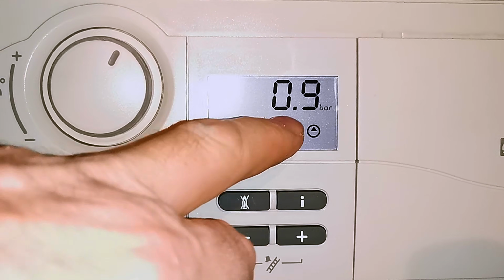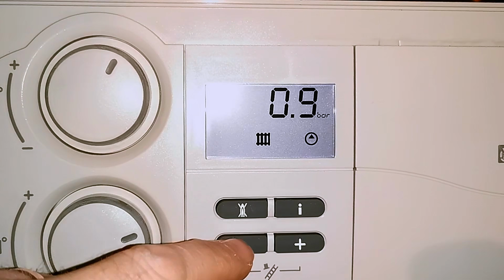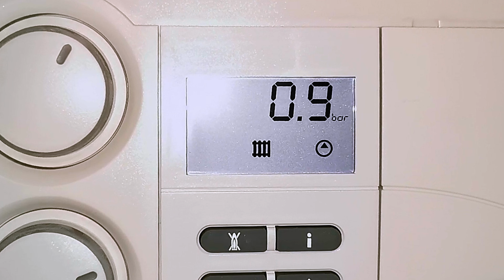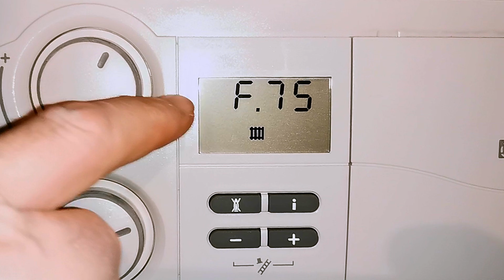Now, if that pressure does not change when the pump runs, then the boiler will lock out with F75. And there you go, the boiler is now just locked out again with F75. And that's because the pressure sensor has become faulty, it's overreading and has become stuck. So it needs to be replaced.